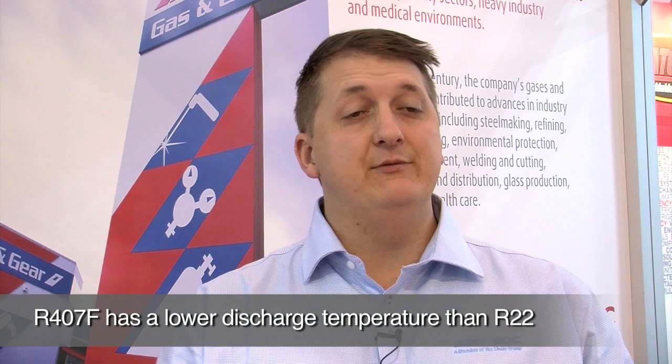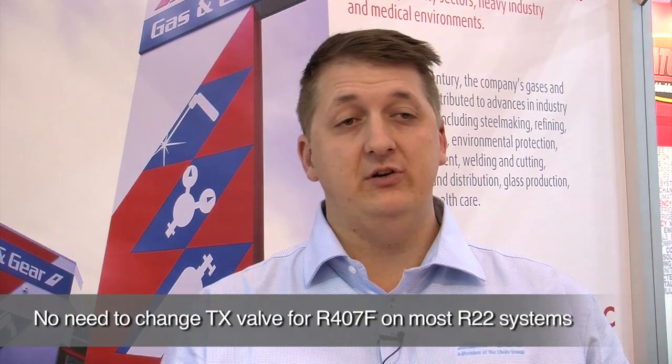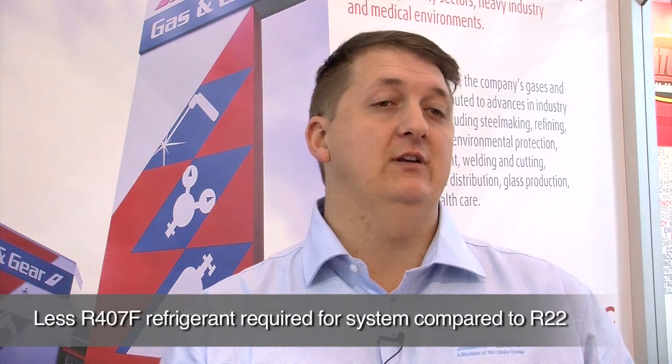The benefits of R407F are that it has a lower discharge temperature, it has the same superheat setting as R22 so there's no TX valve adjustments or changes, it has an easier retrofit process where all you have to do is replace the mineral oil with a polyolester oil, and it actually uses less refrigerant than R22.